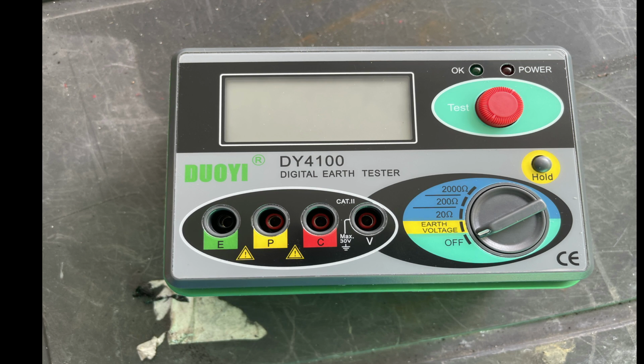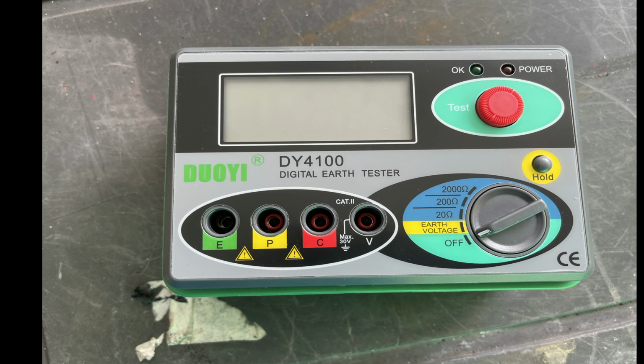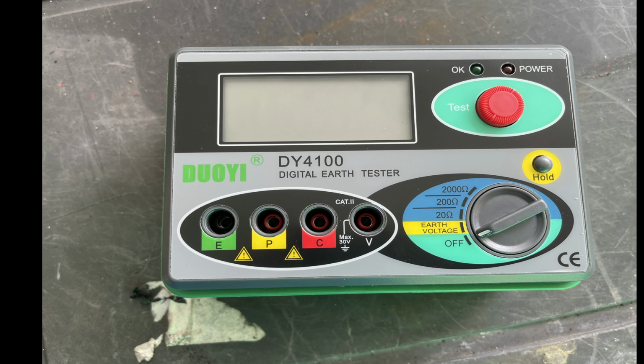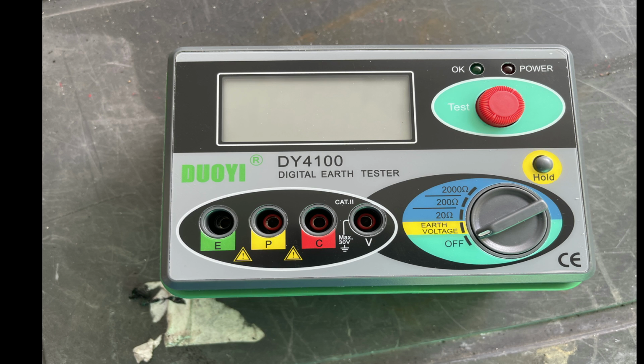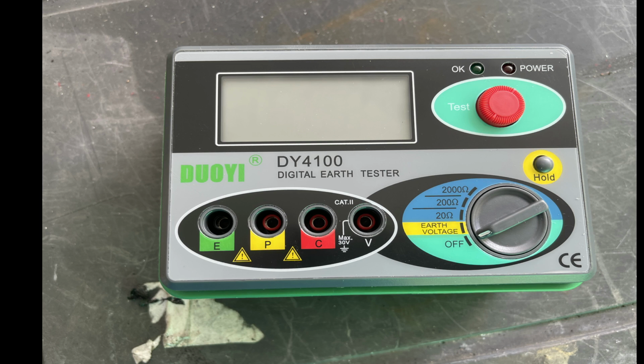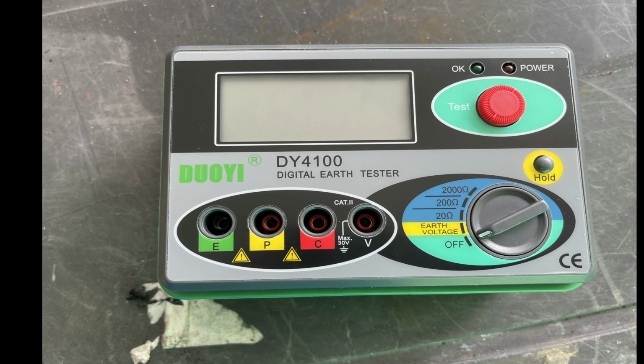To measure soil resistivity, the electrodes are placed in a line or a grid, and the transmitter sends the current through one electrode and measures the voltage drop between 2 or more other electrodes. The distance between the electrodes and the voltage drop are used to calculate the resistivity of the soil. The instrument is commonly used in grounding systems, lightning protection, and electrical safety testing.